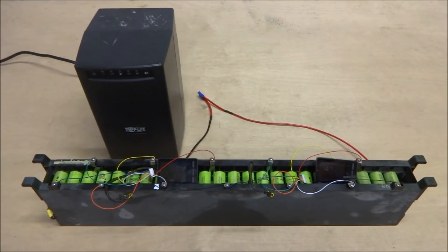Good day everyone. I thought I'd try out running a UPS off of lithium batteries. Now these are lithium iron phosphate batteries, not lithium ion. Lithium iron phosphate batteries have a voltage range which more closely matches that of lead acid batteries.